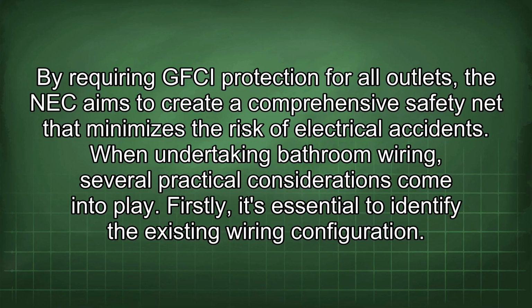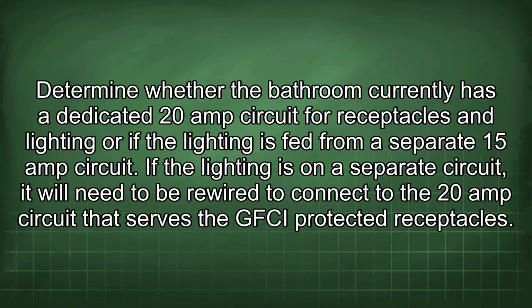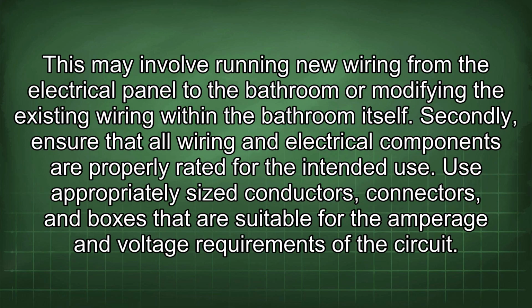When undertaking bathroom wiring, several practical considerations come into play. Firstly, it's essential to identify the existing wiring configuration. Determine whether the bathroom currently has a dedicated 20-amp circuit for receptacles and lighting, or if the lighting is fed from a separate 15-amp circuit. If the lighting is on a separate circuit, it will need to be rewired to connect to the 20-amp circuit that serves the GFCI protected receptacles. This may involve running new wiring from the electrical panel to the bathroom or modifying the existing wiring within the bathroom itself.